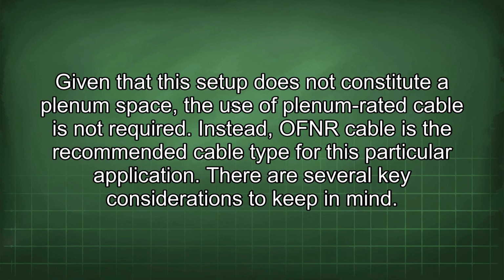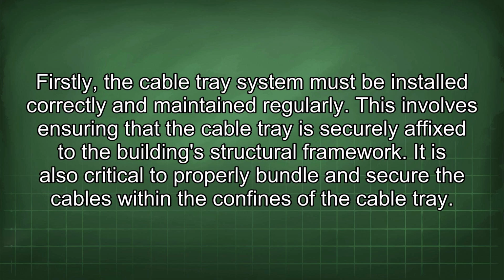There are several key considerations to keep in mind. Firstly, the cable tray system must be installed correctly and maintained regularly. This involves ensuring that the cable tray is securely affixed to the building's structural framework. It is also critical to properly bundle and secure the cables within the confines of the cable tray.